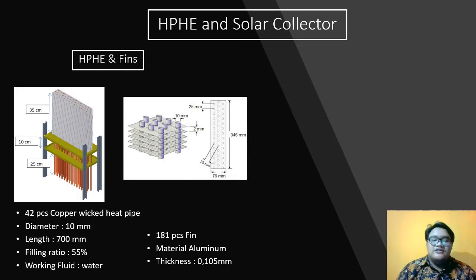The heat pipe heat exchanger uses 42 pieces of heat pipe with a staggered arrangement, 10 mm diameter, 700 mm length, water as working fluid, and 55% filling ratio. It also has 181 fins made of aluminum material with 0.105 mm thickness.